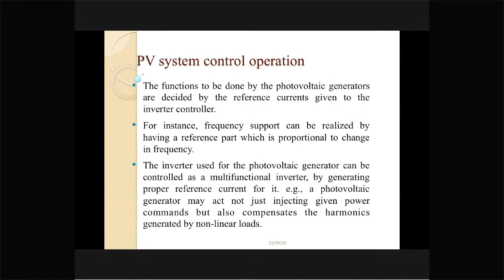So the grid-connected inverter, as I have already mentioned, has a PLL, and then the question becomes whether I will control the current or I will control the voltage. Because it is a grid-connected system, I cannot change the voltage of the grid. So I modify the inverter to act in the current control mode of operation. If we go for the current control mode, then I will inject a certain amount of current into the system, keeping the grid voltage intact. Under that circumstance, I am in fact injecting a given power into the system, and the inverter becomes a PQ mode of operation. I inject a certain amount of P and I inject a certain amount of Q.